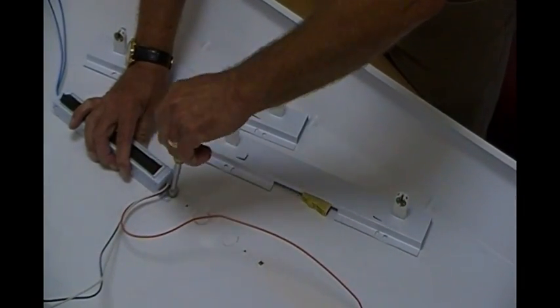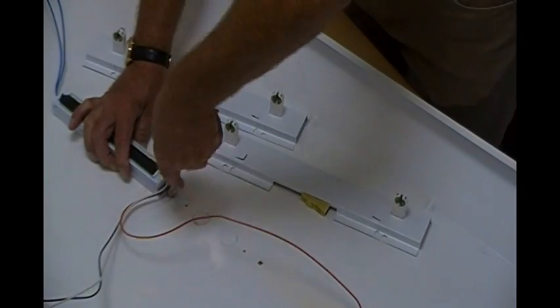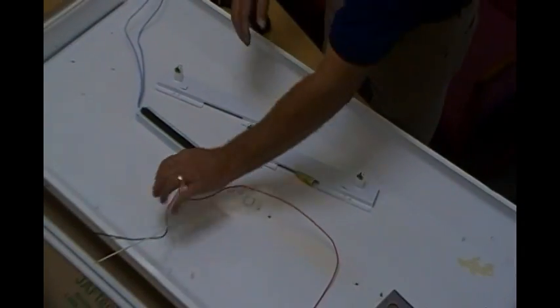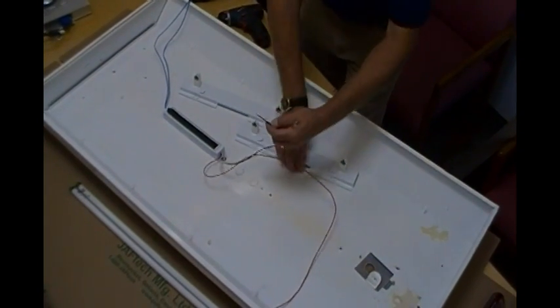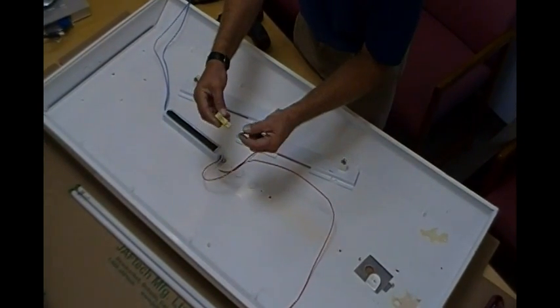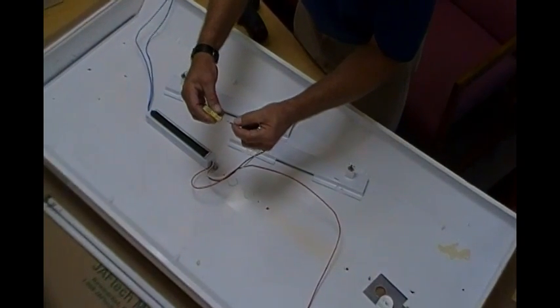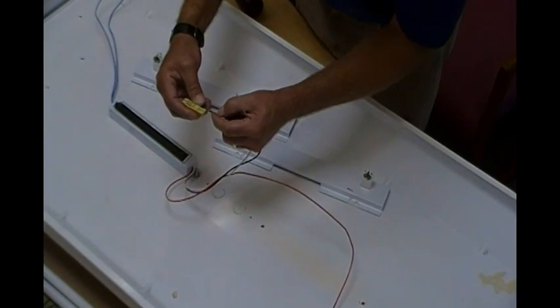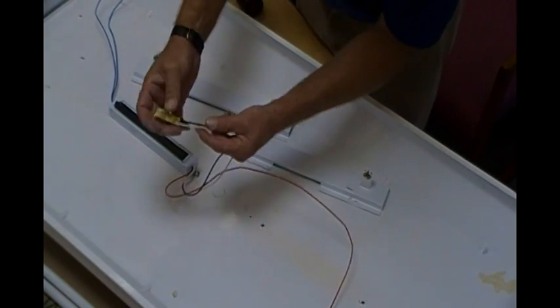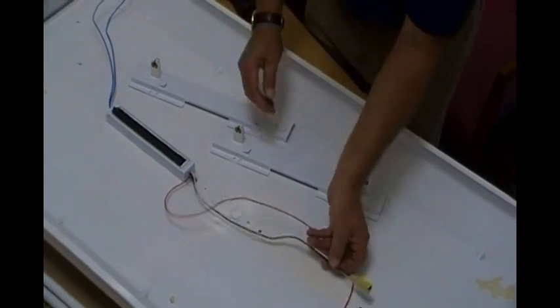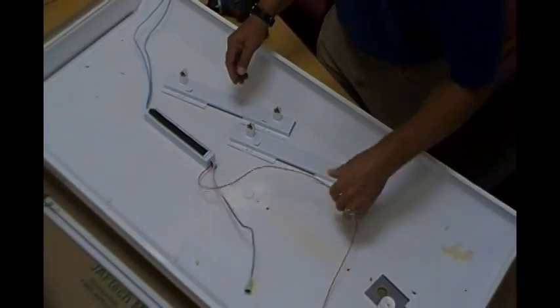Attach your new electronic ballast. Then you'll want to attach your ballast disconnect for 150 volts to ground or higher. The black lead is marked as well as the white, and then your power. The final power connection will be done at the end.